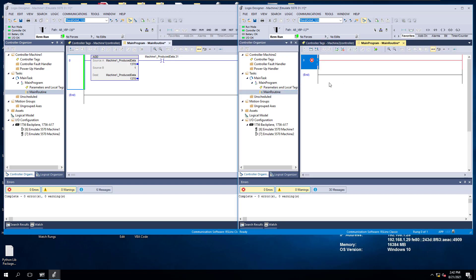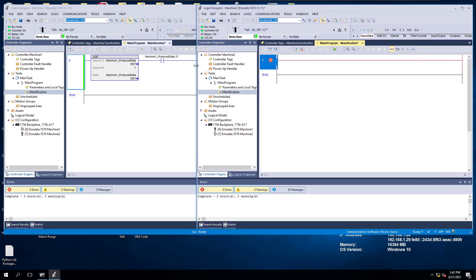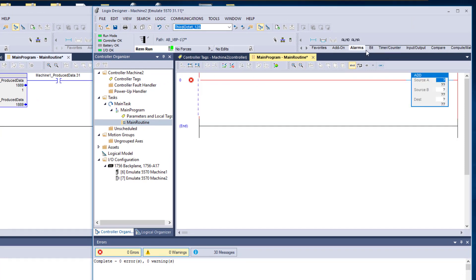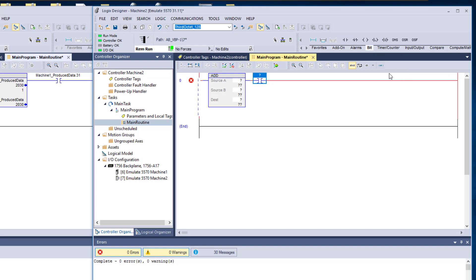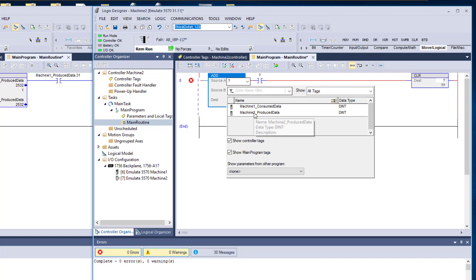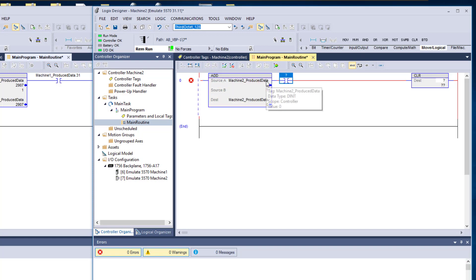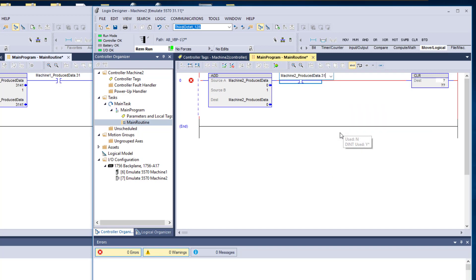We'll do the same thing over here. We'll come over here and do our first rung, spread this out a little bit, get our math function, and do our add. We'll go ahead and add in our bit right here, and then we'll do our clear. We'll come over here and grab our produced data — this is the produced data against itself. We're just going to add a one to it, and then we're going to grab the last instance of this, which is bit 31.